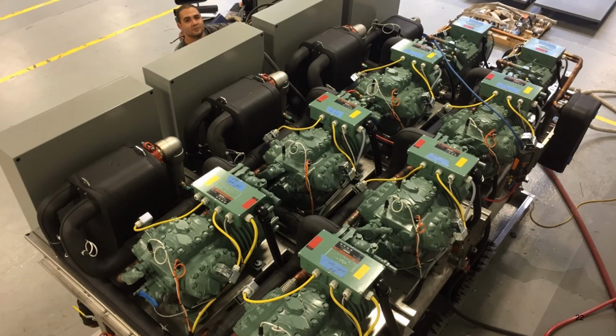Here's a photo example of such a chiller. In this case, it's being tested at the factory. In this scenario, there are actually 4 chiller modules. 3 chiller modules are cooling only, and then the last 4th module has an auxiliary condenser specifically sized for the hot water load. The cooling capacity of the 4th module counts towards offsetting the total cooling load, since the unit can switch between rejecting heat to the cooling tower and recovering heat for the boiler loop.